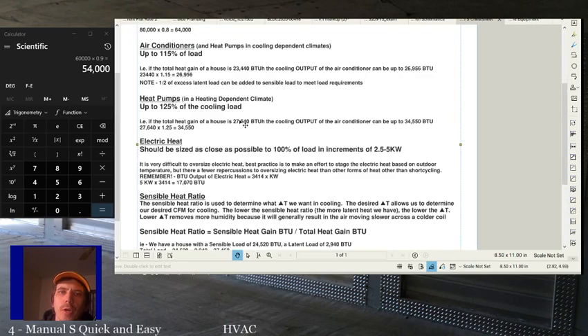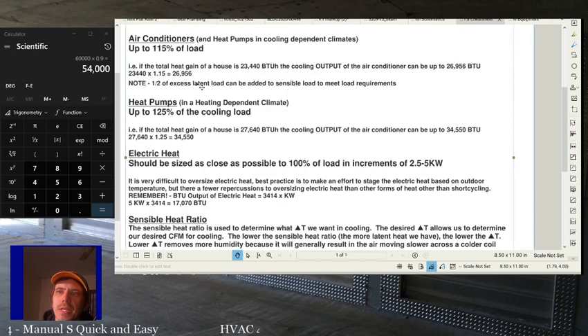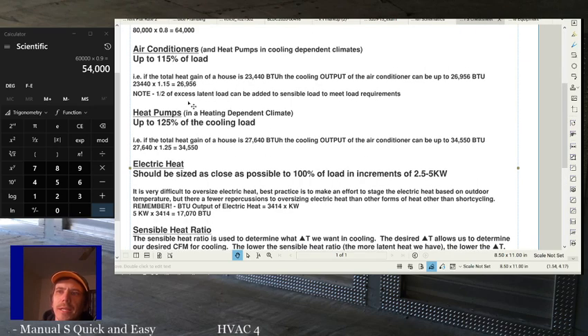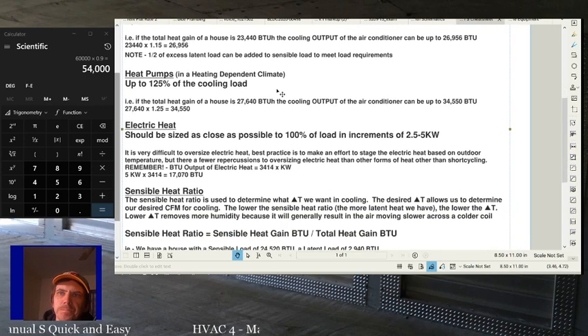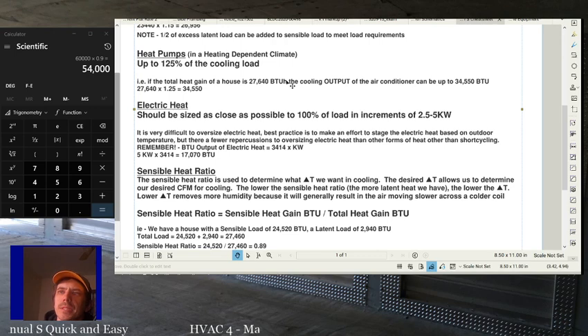That way we can throw a couple numbers out there, but just understand that if you have more latent capacity than you need, half of what's left can be added to meet your sensible if the sensible load of the equipment's not enough. All right. So that note's just there so I could put it somewhere on the sheet. There's no other real good place to add it in there. So I just added it under air conditioners just so you'd have that note if you ever needed it. All right, heat pumps in a heating dependent climate, you can do up to 125% of the cooling load.